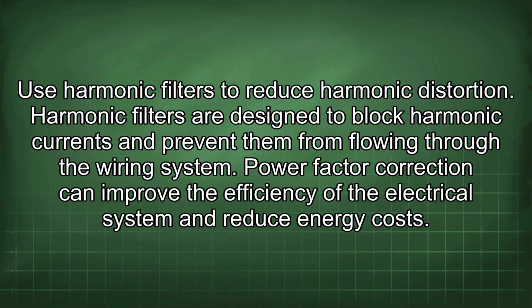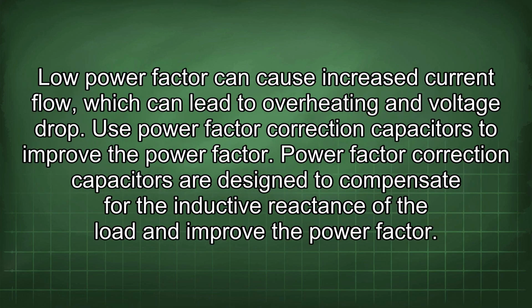Power factor correction can improve the efficiency of the electrical system and reduce energy costs. Low power factor can cause increased current flow, which can lead to overheating and voltage drop. Use power factor correction capacitors to improve the power factor. Power factor correction capacitors are designed to compensate for the inductive reactance of the load and improve the power factor.